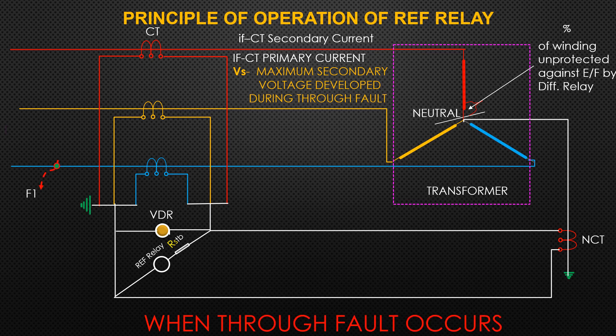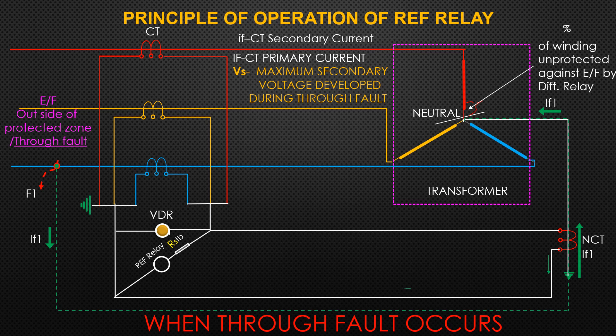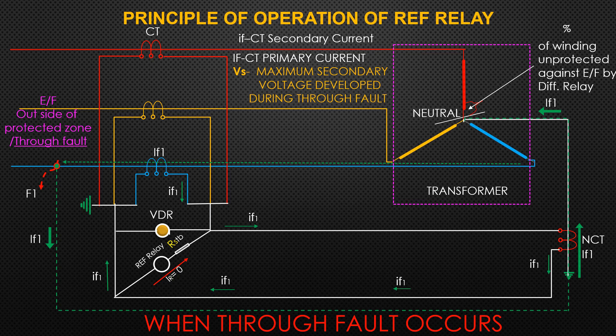When there is a fault outside the protected zone, the CT secondaries will cancel each other's currents. This is partly true even if both or only one of the CTs saturates, because the impedance of a saturated CT secondary will collapse to near zero. The non-zero wiring impedance and CT impedance will however cause a voltage, but the stabilizing resistor will prevent the relay from tripping.